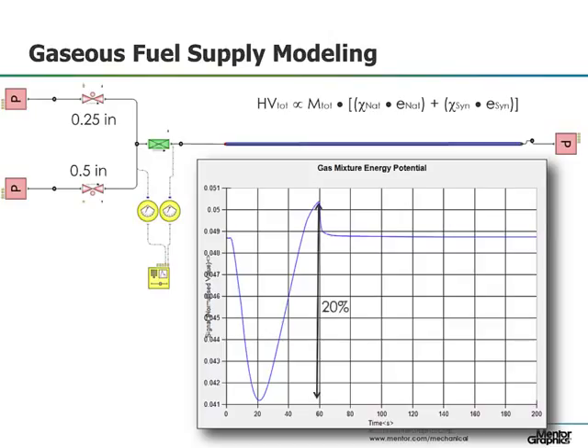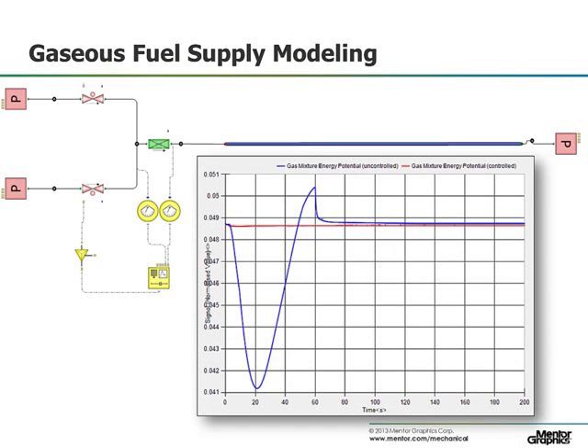It is clear that despite our attempts to equalize heating value of the two fuels through valve sizing alone, we also need to control valve rate, as we see a 20% variance in heating value during the transition from one fuel to another. We can remedy this problem by using our heating value parameter result from the controller and using it in conjunction with a PID controller to operate the syngas feed valve for us at a controlled rate. Looking at our heating value results again after this change, you can see now that the controlled heating value variance is almost non-existent.